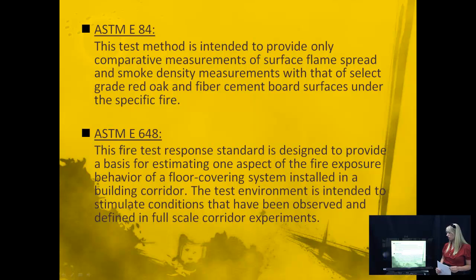The next one is ASTM E648, and it's a fire test response standard. It's designed to provide a basis for estimating one aspect of the fire exposure behavior of a floor covering system installed in a building corridor. The test environment is intended to simulate conditions that have been observed and defined in full-scale corridor experiments. So just remember the ASTM E84 is a test method, and the ASTM E648 is a test response standard.